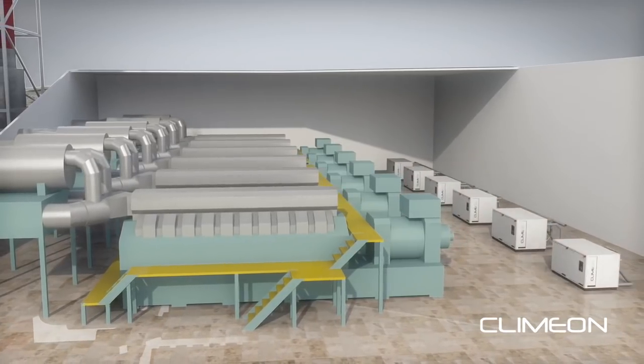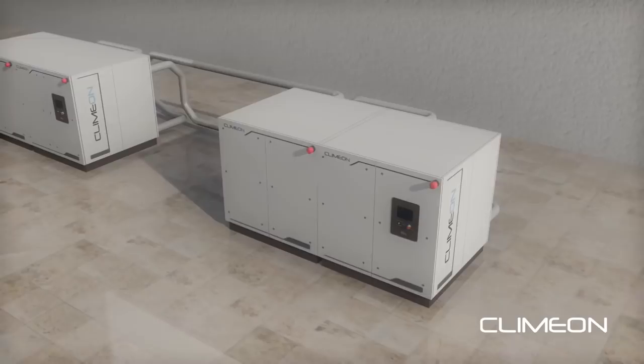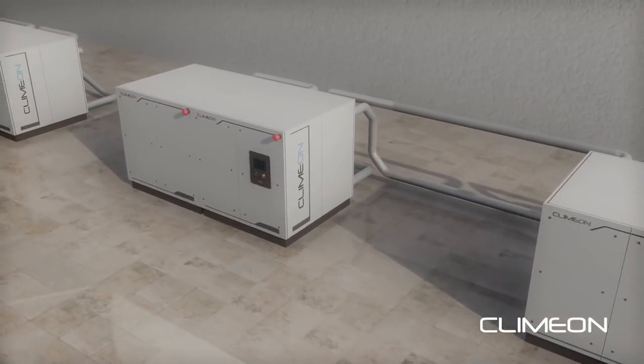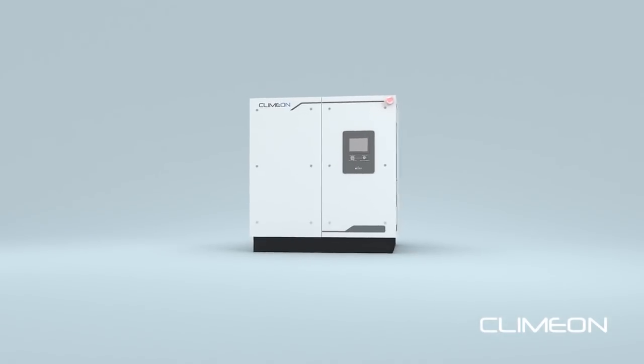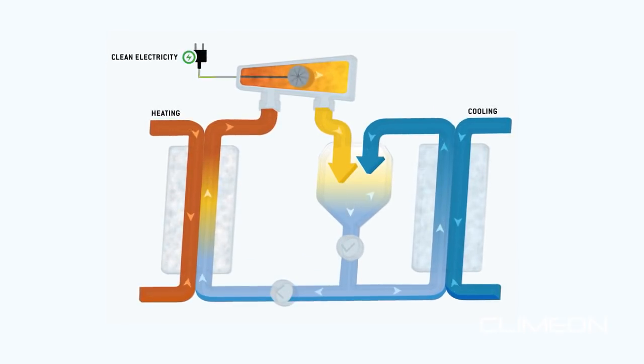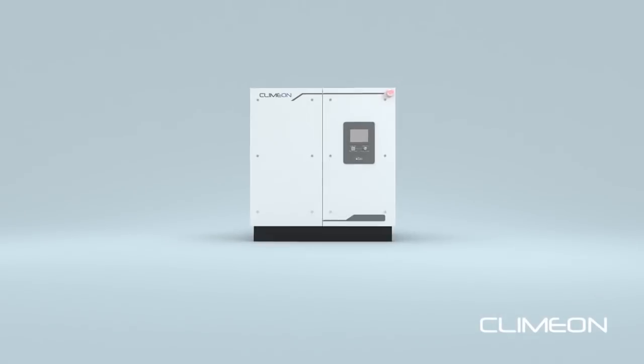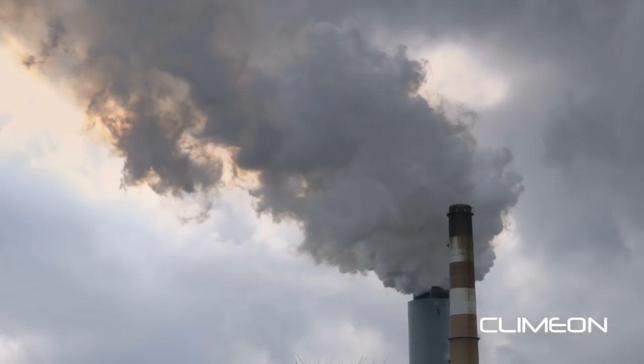By adding Climeon Heat Power to capture the waste heat found in the exhaust gas and engine cooling water, the electrical production can be increased by up to 10 percent. The process is actually quite simple. The Climeon Heat Power system exploits the temperature difference between hot and cold water to generate clean electricity and improve overall efficiency, resulting in increased power production for the same fuel input, which reduces the plant's environmental impact.